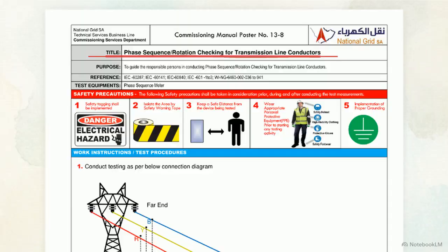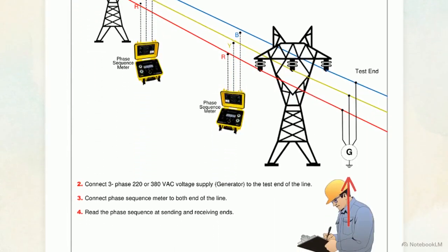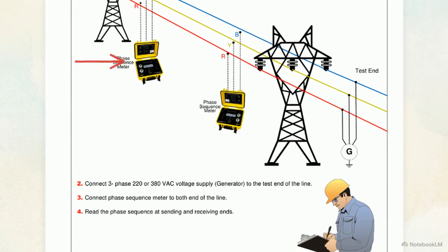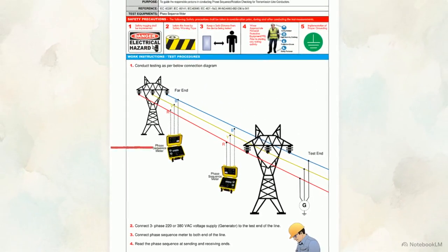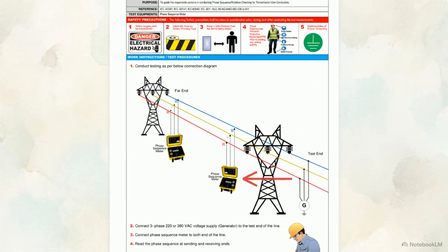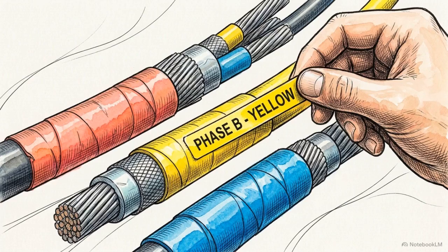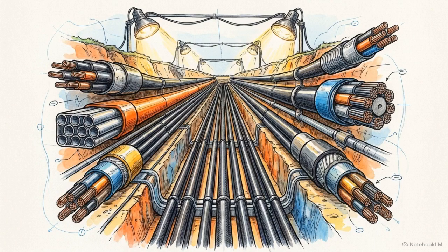This schematic details Test 13-8, phase sequence and rotation checking. A three-phase AC supply is connected at the test end. Technicians utilize sequence meters at both sending and receiving ends to read phase rotation simultaneously without changing test leads during the comparison. Any phase reversal, crossed conductor, or labeling error must be corrected. Surviving the intense voltage stress and proving a mechanically identical RYB sequence at both ends guarantees the physical grid architecture is cleared for live parallel power.